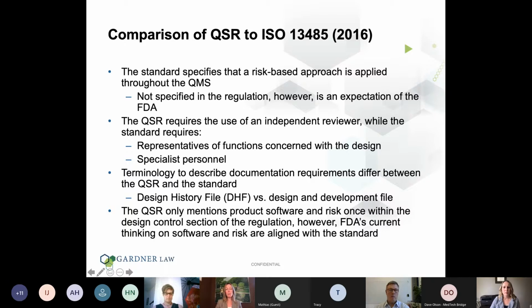So this comparison that I have here to the 13485 standard is highlighting some of the differences, if you already have compliance with ISO 13485. Sorry, it's the other way around. This is the additional requirements that you would have to add onto a 13485 compliant quality management system in order to also be compliant with the FDA's quality system regulation.